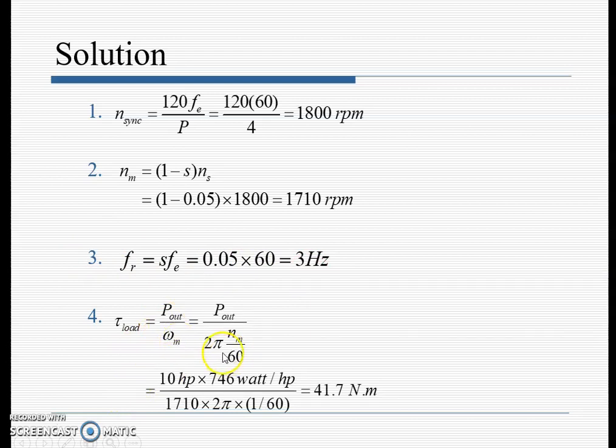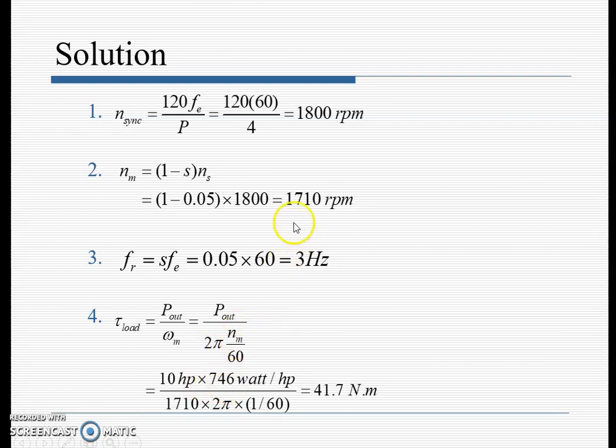For the shaft torque: T = P_out / ω_m, where ω_m = 2π·n_m / 60. P_out is 10 HP, which we convert to watts by multiplying by 746. With n_m = 1710 rpm, the shaft torque comes out to be 41.7 Newton-meters.